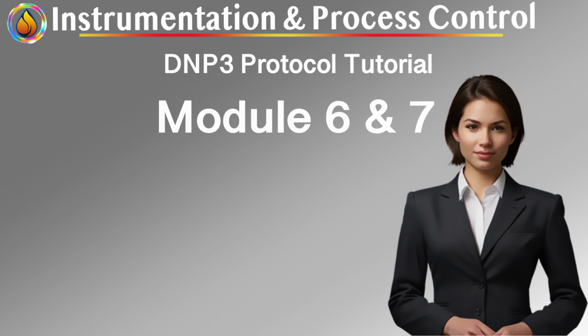6.3 Multi-drop, multi-point architecture. Structural characteristics. In a multi-drop architecture, one master communicates with multiple outstations. Devices share a common communication medium. Each outstation has a unique DNP3 address. Only one device transmits at a time under master control.